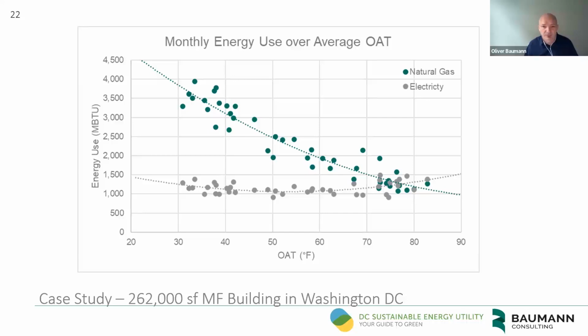And so the green dots is the natural gas consumption monthly, again plotted over the monthly average outdoor air temperature. And what we see here is exactly what we would expect, that with lower outdoor air temperatures, that is to the left, the monthly natural gas consumption goes up because we have more heating demand. And as the temperatures rise, we have warmer months, 60, 70, 80 degrees monthly average, the natural gas consumption goes down because the heating demand goes down. However, what we would like to see in a very efficient building is that natural gas consumption goes almost down to 0, except for that natural gas that you might need for domestic hot water and cooking or other uses that you identified earlier in your energy use breakdown.